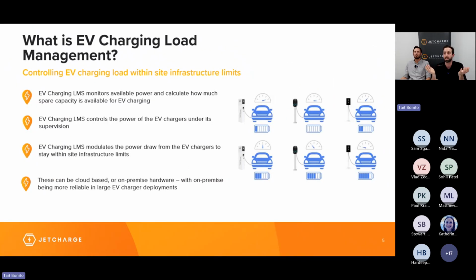What even is EV charging load management, and what problem are we trying to solve? EV charging load management systems are used to control the total power output of EV chargers at a specific site. Unlike other common electrical loads, EV chargers can draw really high power, starting at around 32 amps for a single charger but going up to hundreds of amps per phase depending on the power rating or number of chargers at a site. EV chargers draw this high load continuously and at a sustained level, unlike other appliances where there's a small peak as power draw ramps up and then tails off - EV chargers pull 32 amps or hundreds of amps consistently and continuously.